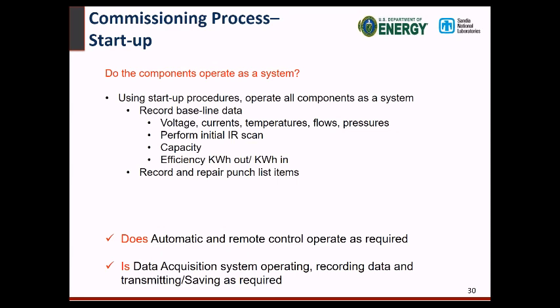So in the process, when you're doing the startup, basically you want to record a baseline when you turn it on. You want to make sure all the voltage and currents are right. You want to make sure that your meters, what they're putting out, showing you this is the voltage and currents. Use another ammeter just to verify and make sure all your meters are calibrated.